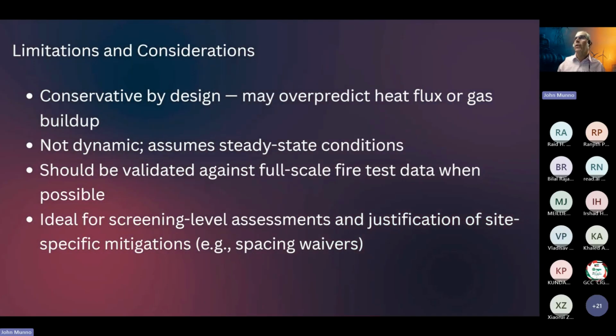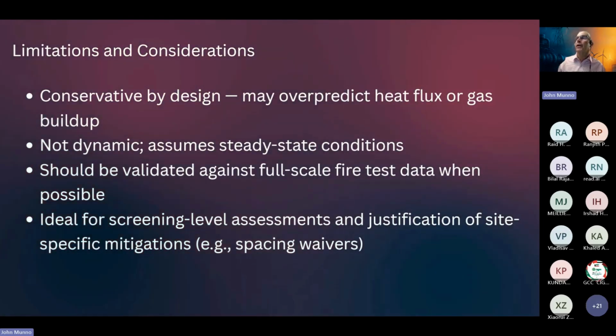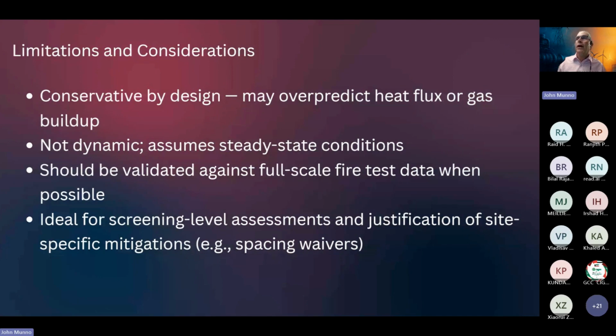But just be aware that they're conservative by design. They may overpredict the heat flux or the gas buildup. They're not dynamic; they assume a steady state fire. When we do a full scale battery fire, it starts small. It starts in one cell and then grows. That should be taken into consideration. If you can do a full scale test, try to validate these models against the full scale tests. But for screening, it's ideal. It's good for justification of site specific mitigations like spacing waivers, like trying to convince the insurance company that your spacing is adequate without doing a test. So these are some of the limitations and considerations.